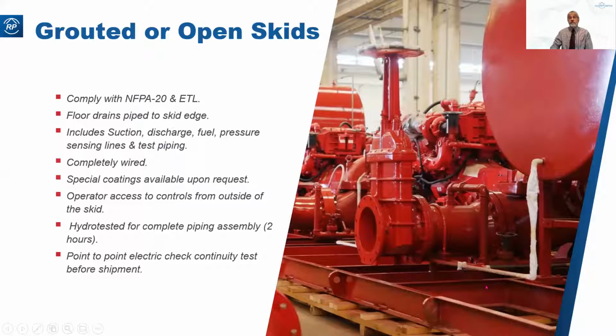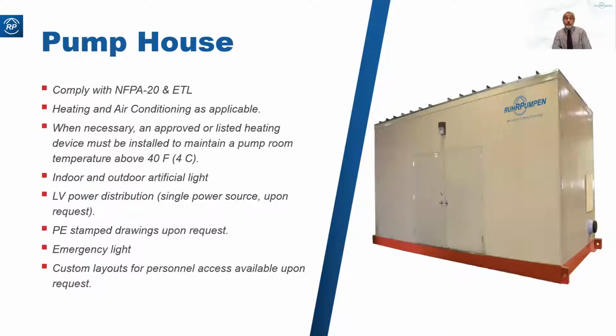The base plates, the skid type base plates, they can be grouted or ungrouted. These are invariably engineered products. Each one will be different, specific to what you want. Complete pump houses are increasingly popular for oil and gas projects in particular. These housings are frequently flame resistant, fire resistant housings. A typical one might be H60 enclosure, which means it will withstand a hydrocarbon fire for 60 minutes. You also get H120 and H180.